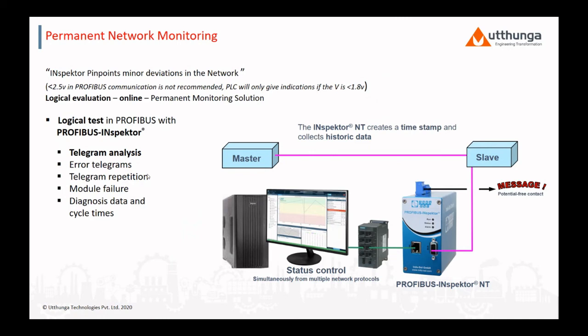Is there any tool for identifying the logical problems? Definitely, we have a tool, the Indu-Sol manufactured PROFIBUS Inspector. You can identify all logical problems and you will get a warning before failure of your networks. Normally this tool does continuous monitoring. If you want a warning before failure, you need to install this tool 24/7 for continuous monitoring, near your master system. You can see here the complete connection of your master system with the Inspector.